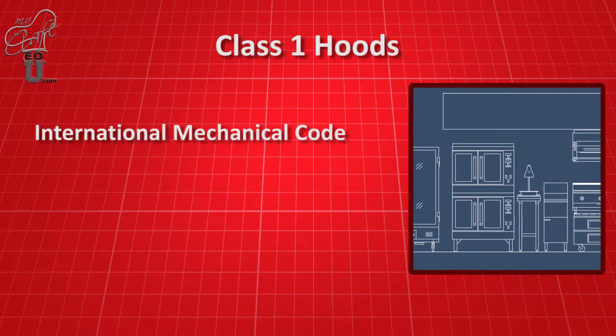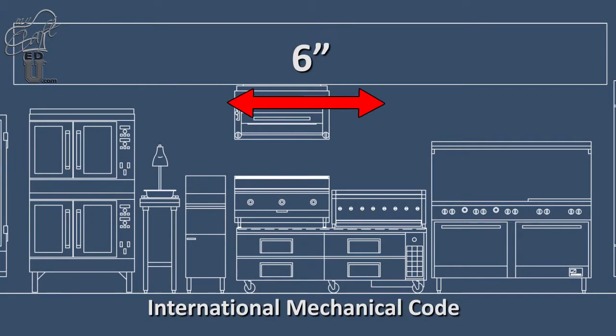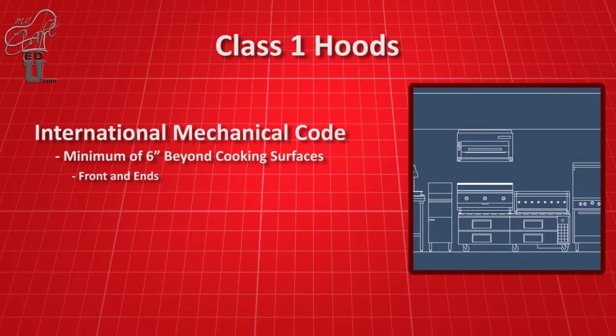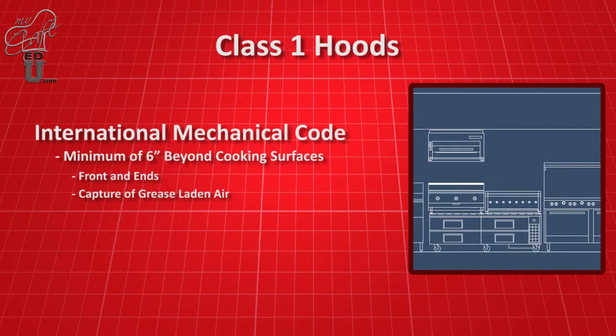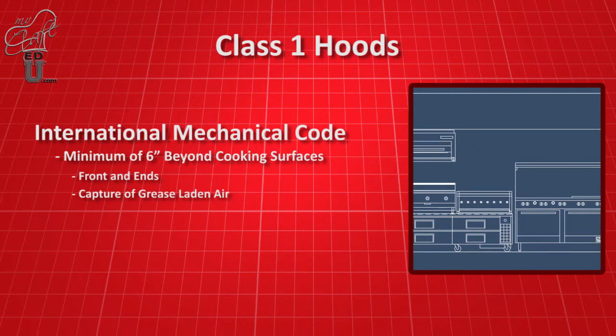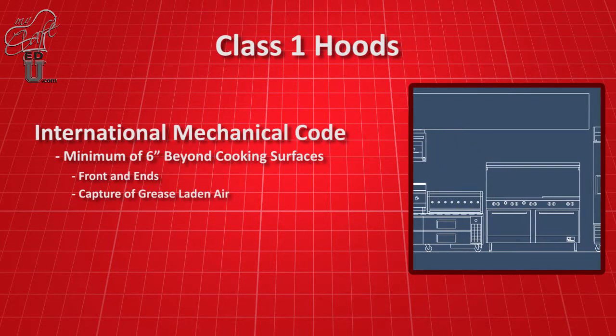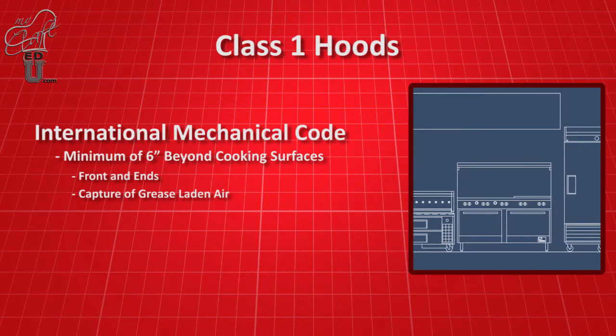The International Mechanical Code requires that canopies must extend beyond all cooking surfaces by a minimum of 6 inches on the front and ends. This is to ensure the hood is large enough to capture the rising, hot, grease-laden air as it expands up and away from the cooking surface.